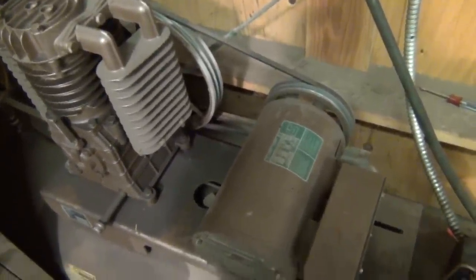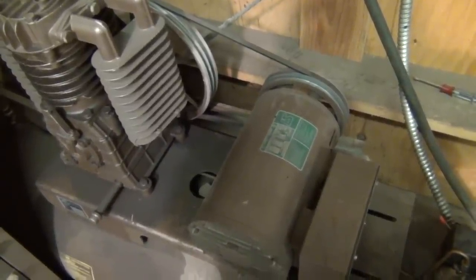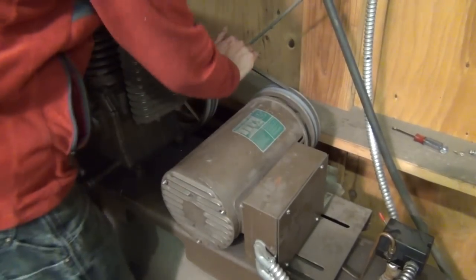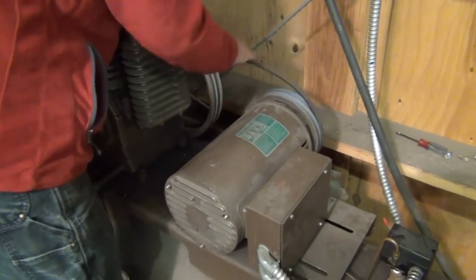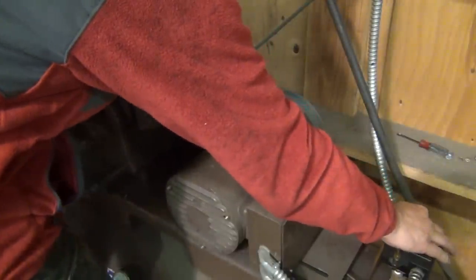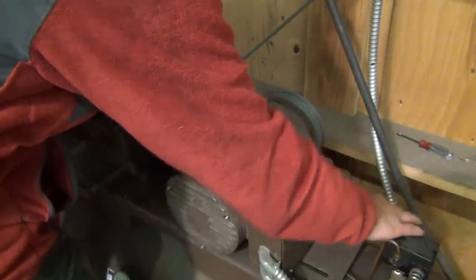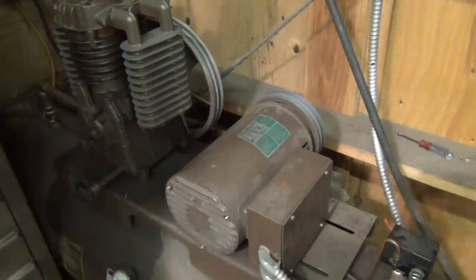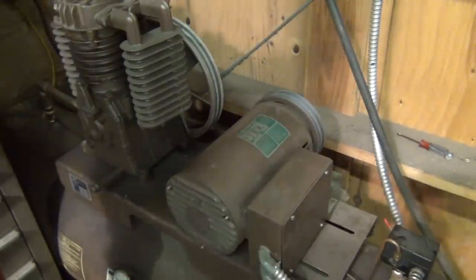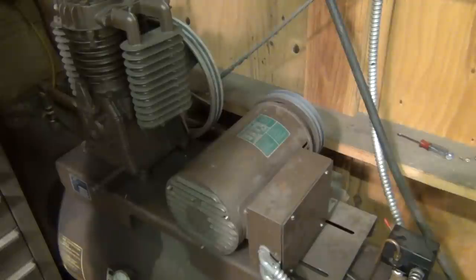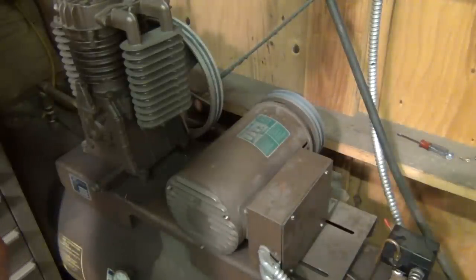But before I do that I'm going to pop the belt off and just make sure that the motor actually does come up to speed, listen to it and make sure there's no funny smells or smoke or anything coming from it. Alright well the motor sounded just fine. I didn't detect anything odd there at all so I definitely suspect that it's that start capacitor. We'll go ahead and take that cover off and get to some troubleshooting.